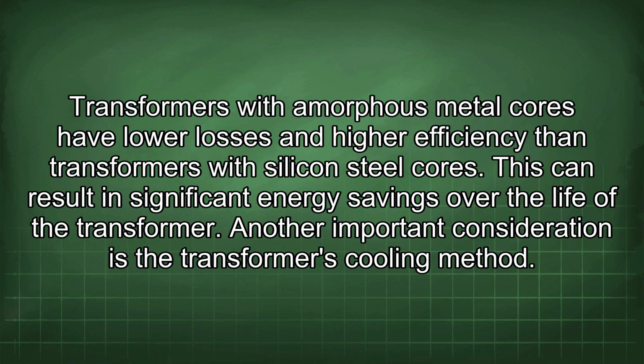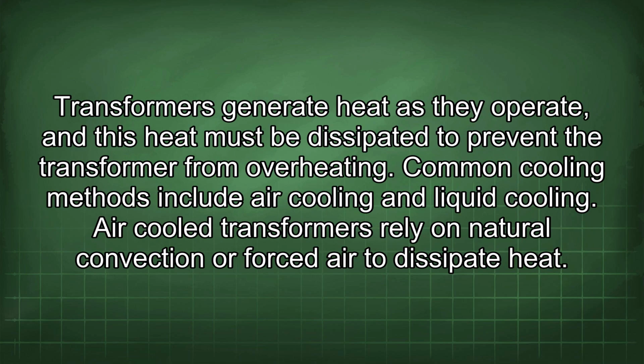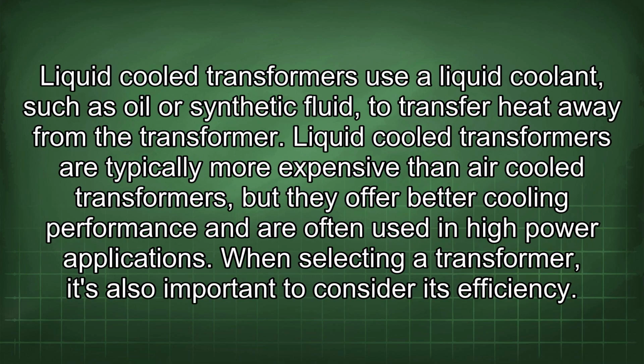Another important consideration is the transformer's cooling method. Transformers generate heat as they operate, and this heat must be dissipated to prevent the transformer from overheating. Common cooling methods include air cooling and liquid cooling. Air-cooled transformers rely on natural convection or forced air to dissipate heat. Liquid-cooled transformers use a liquid coolant, such as oil or synthetic fluid, to transfer heat away from the transformer. Liquid-cooled transformers are typically more expensive than air-cooled transformers, but they offer better cooling performance and are often used in high-power applications.